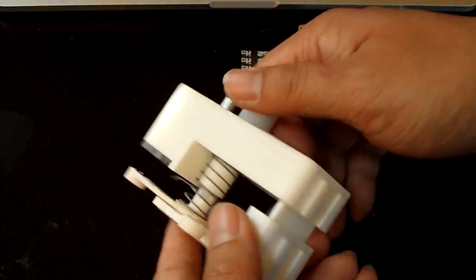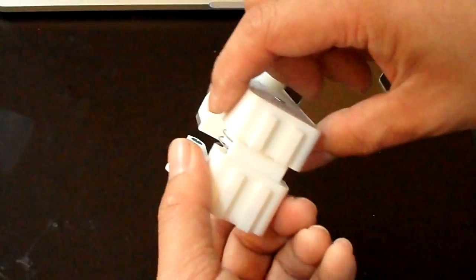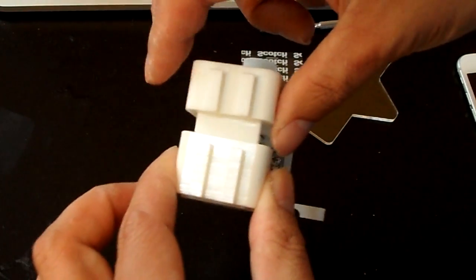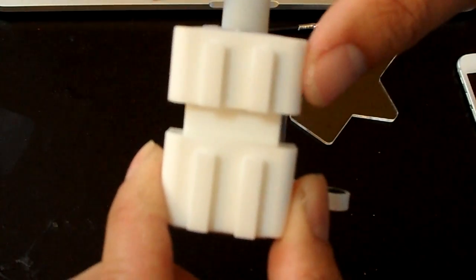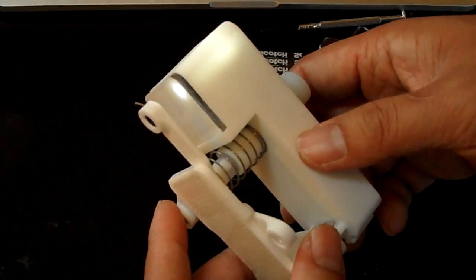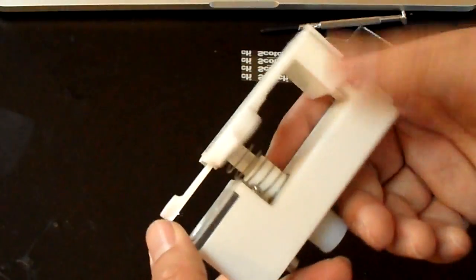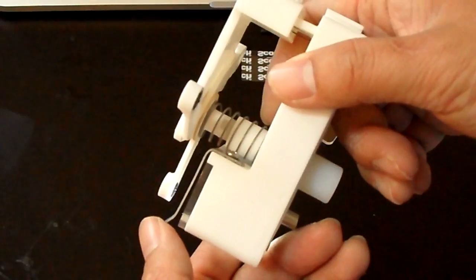And the reason why is because as you're turning the focusing knob, it tends to move the top half relative to the bottom half. As you can see, there's a little bit of slop. But this anti-rotation spring here will make sure that the microscope returns back to the same position, so that after you've centered it, it will stay centered.